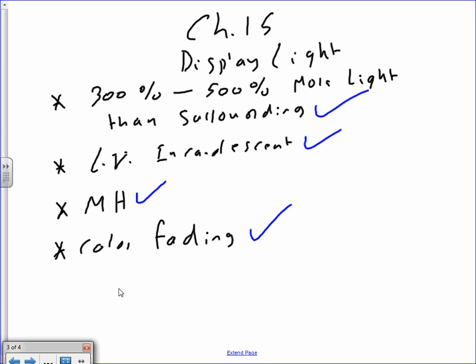Anyway, if you look at that one, the other one on the right side is tungsten halogen. Let me look at the first one. One fixture is Q20 MR16. I don't know if these are even still on the market, but rated life 3000. They give you a beam spread of 7x5, a bigger beam spread. Based on the distance, if I put them 7 feet from the object, they can give me 183 lumens, and the beam length and width are given, as well as the maximum spacing. Maximum spacing for even illumination is 1 foot away from each other.